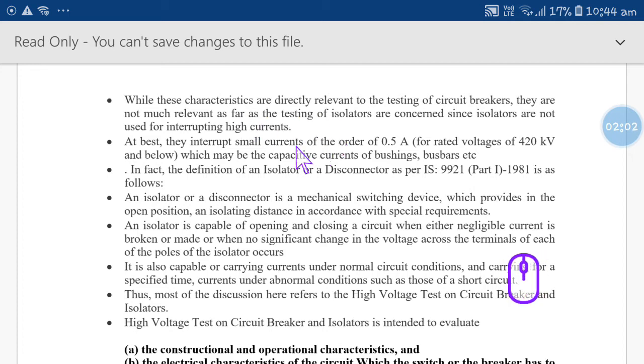Testing of isolators as well as circuit breakers has to be done. Here you can see a small interrupting current of the order of 0.5 ampere for rated voltage of 420 kilovolt and below, which may be a capacitive current of bushings, and some voltages are specified here, showing how much voltage it can withstand.